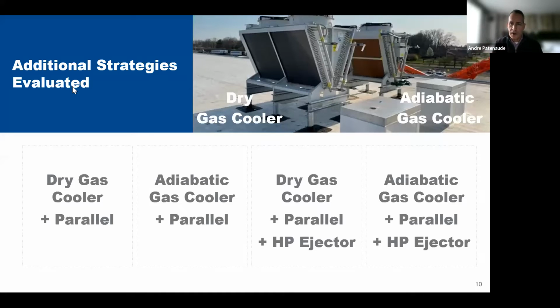Of course, dry cooler is not a high ambient strategy, but adiabatic is. So I say, okay, parallel compression is another technology that can help with energy efficiency. So let's look at that. And then let's look at adiabatic gas cooling with parallel compression or intermediate stage compression. And then we want to look at dry gas cooler, if you've got issues with water availability, with parallel compressor and gas ejectors, high pressure gas ejectors, and then again, adiabatic with parallel. So the next slide kind of breaks it down a bit.